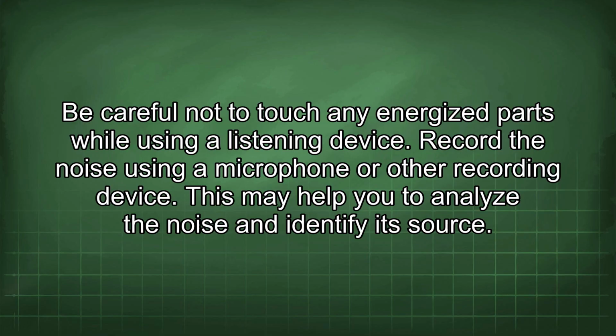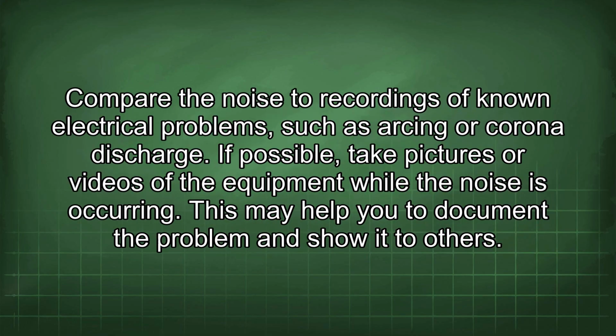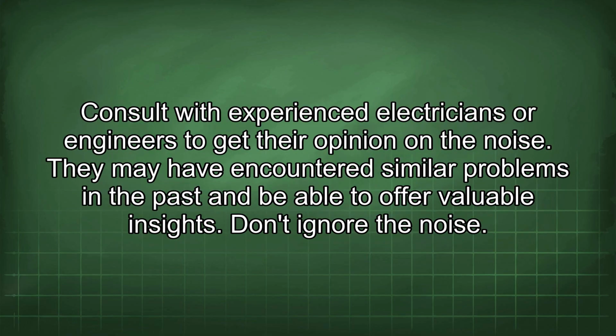Record the noise using a microphone or other recording device. This may help you to analyze the noise and identify its source. Compare the noise to recordings of known electrical problems such as arcing or corona discharge. If possible, take pictures or videos of the equipment while the noise is occurring. This may help you to document the problem and show it to others. Consult with experienced electricians or engineers to get their opinion on the noise. They may have encountered similar problems in the past and be able to offer valuable insights.